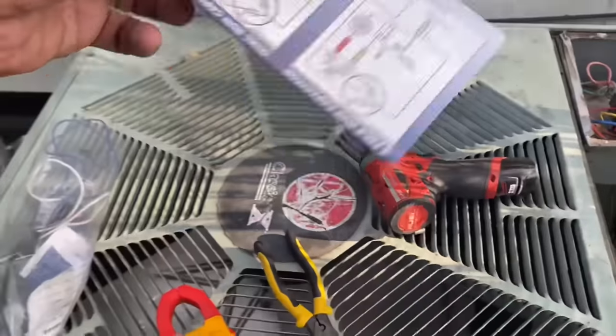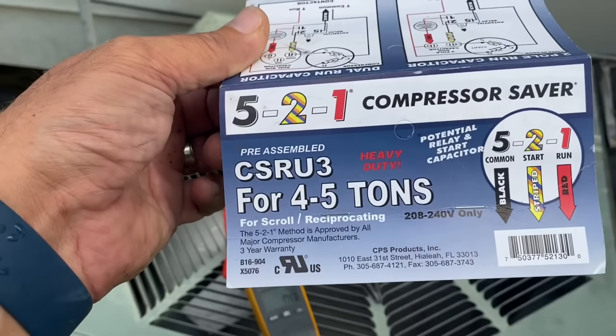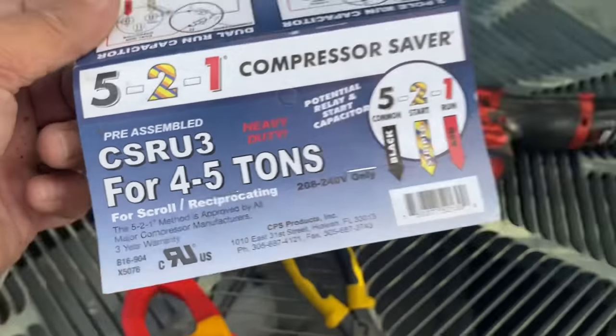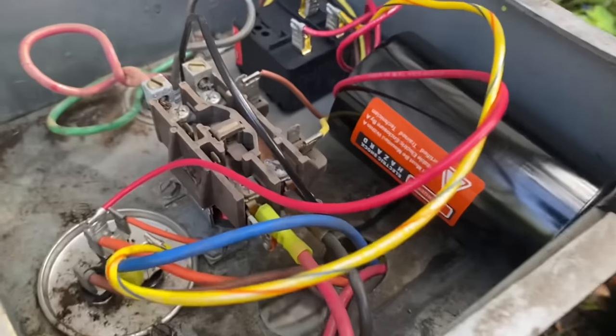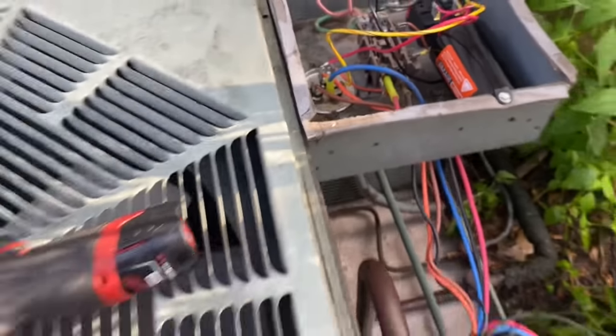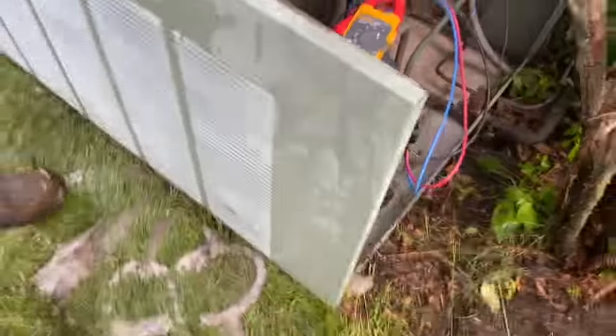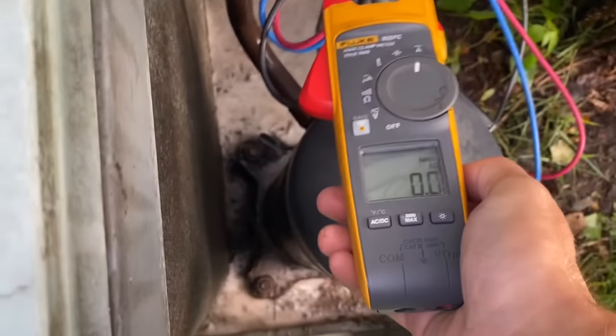I took out the old run capacitor with the relay and I'm using the 5-2-1 compressor saver for four-to-five tons, for scroll or reciprocating — very easy to wire. Secured the little relay box right there, the cap right there, there's our contactor. Wire looks to be okay, everything else looks to be okay. Let's plug the power in and test amperage — Peter, hold that on the amperage while I plug this in.